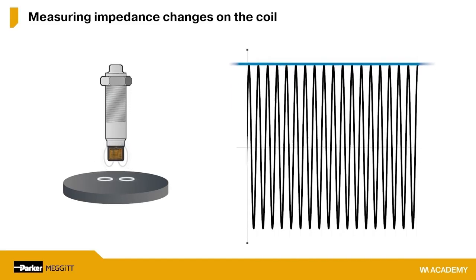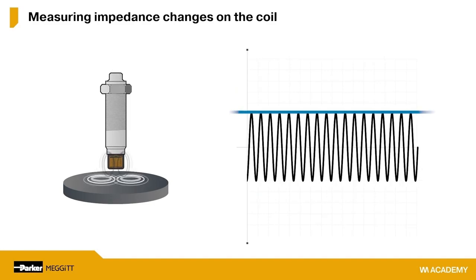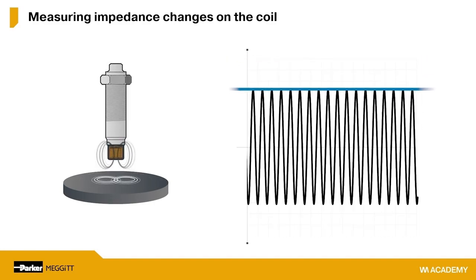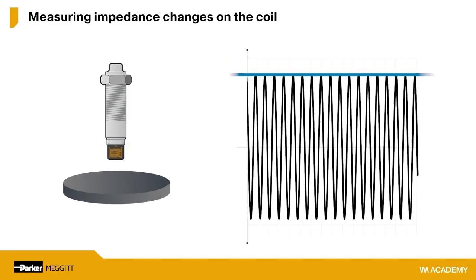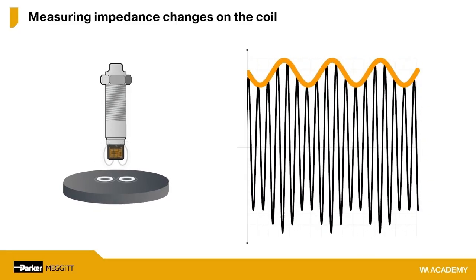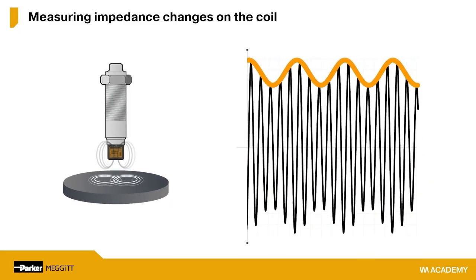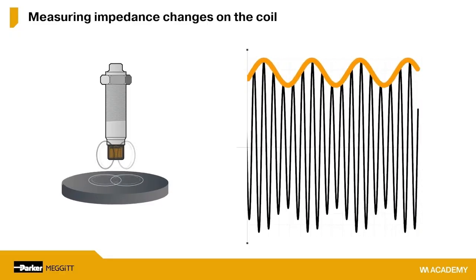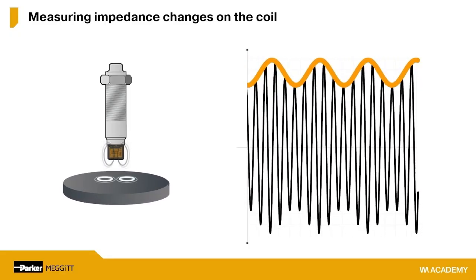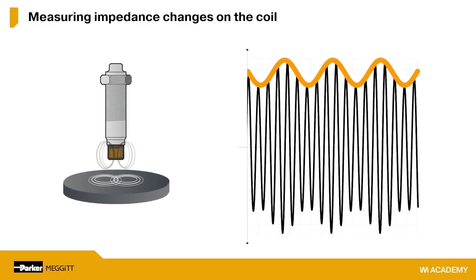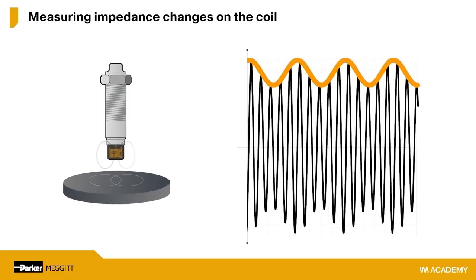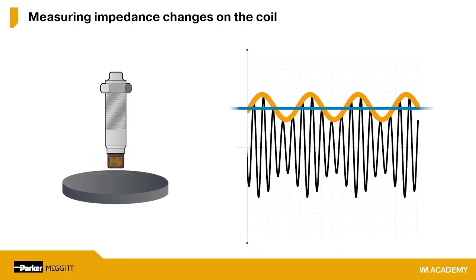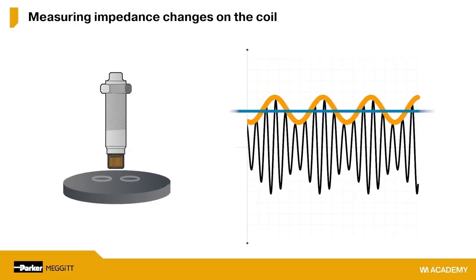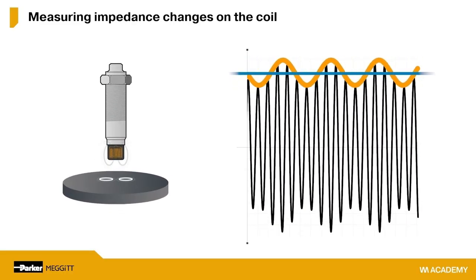This is the static position of the target. Then, if that target starts to vibrate, it starts to move fast, the amplitude of the carrier signal is going to change accordingly. It's going to change fast. And this is what you see here represented as the orange signal. So we have both the AC component and the DC component on the modulated amplitude of that carrier signal.